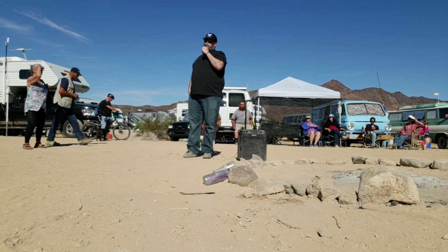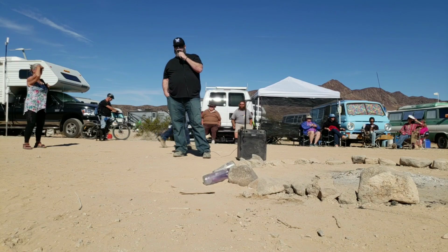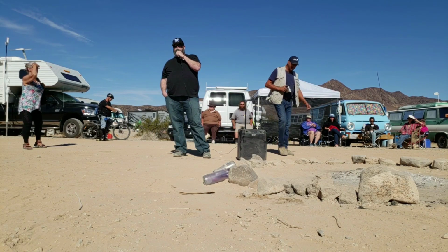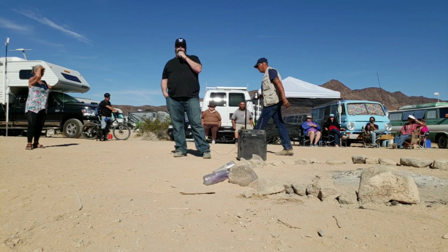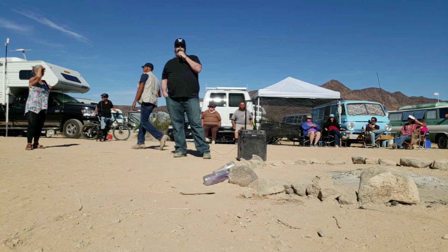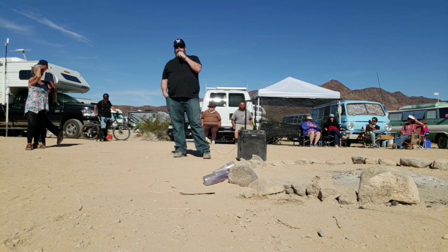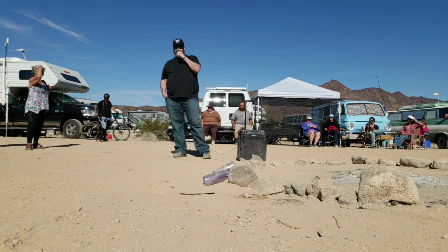So our batteries are a little more expensive than a lead-acid battery up front, but they actually last. After 5,000 cycles in most use cases, you're going to have 75 to 80% of the power left. If you cycle it every day for 10 years, that's 3,650 cycles. So that's why we offer the 10-year warranty.